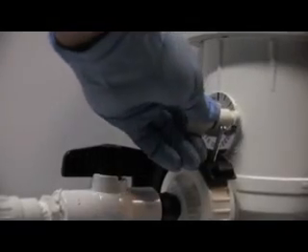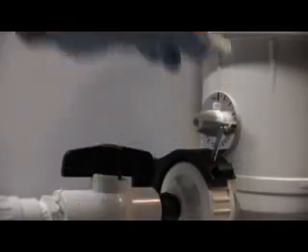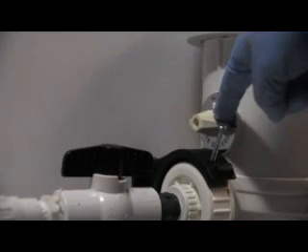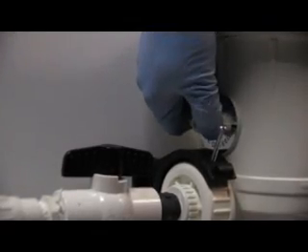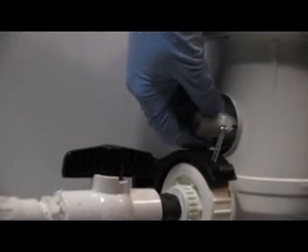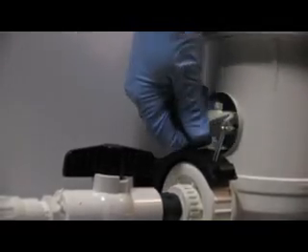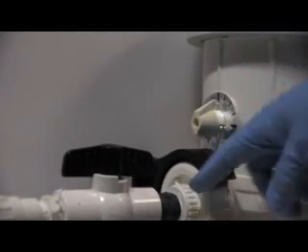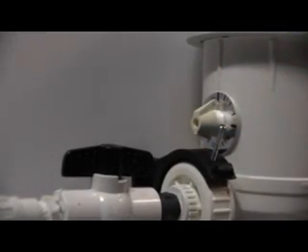And that hole on this dial attachment, or dial option, allows it, by its engineering, that when you turn it, and I'm trying to get my hand position where you can look at it, when I turn it, the hole opens and closes larger. So technically speaking, this dial is by the size of the hole. Here is fully open hole. This is fully closed hole. That's how it meters the chemical in here with this design.